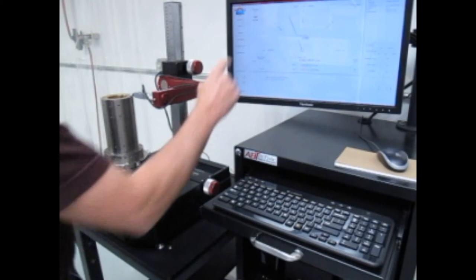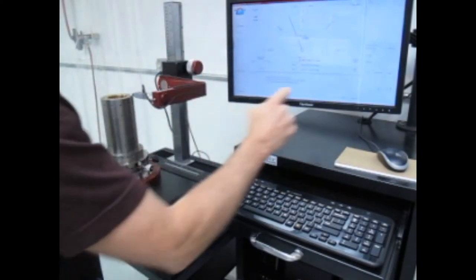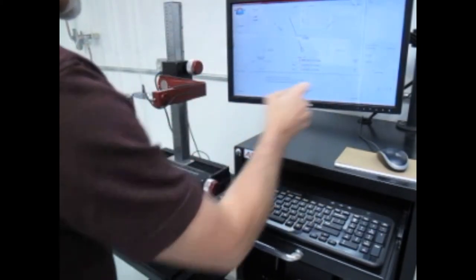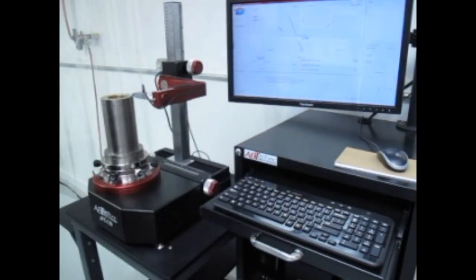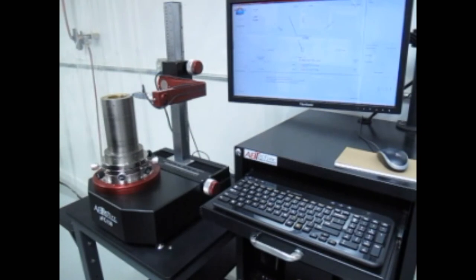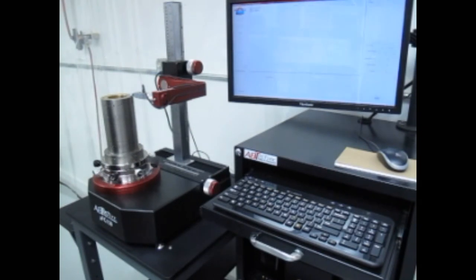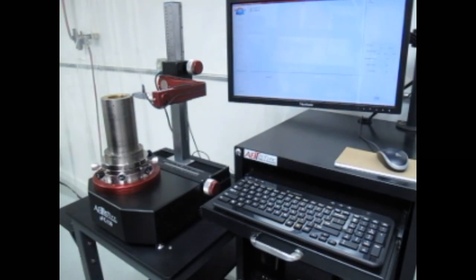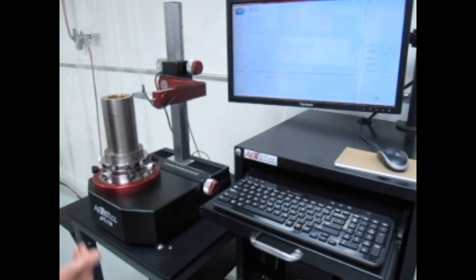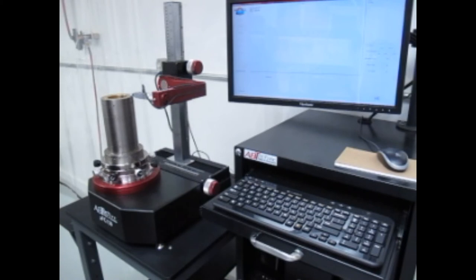So now I'm going to select from the menu flatness and use the motor. And again, it'll take one revolution, it'll orient all of that information relative to the encoder position, so it doesn't have to take multiple rotations until it hits the encoder zero.